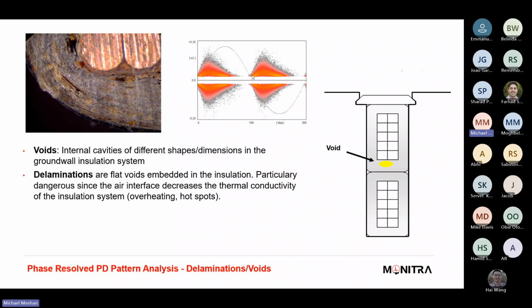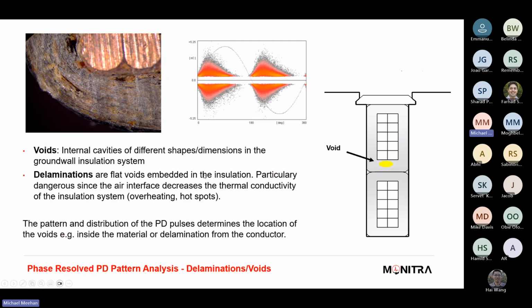So delaminations are flat voids embedded in the insulation, particularly dangerous since the air interface decreases the thermal conductivity of the insulation, so it's trapped against the base of the machine, as it were. So you've got higher temperatures there, less air circulation, and you get these hot spots, and you get these potential issues in the winding. So the pattern and the distribution of the PD pulses determines the location of the voids inside the material or delamination from the conductor.